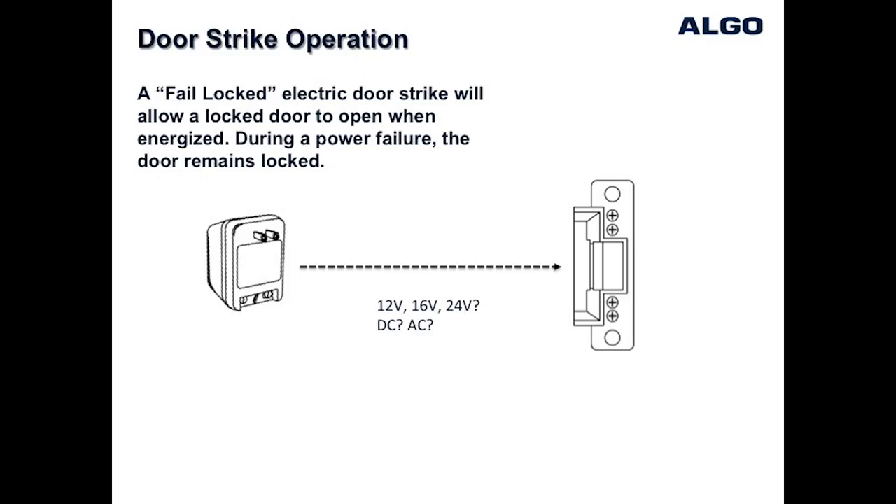There are many types of door strikes depending on the type of door jamb, and many operate at different voltages, such as 12, 16, or 24 volts DC or AC. It's important to know which voltage your door strike requires, and also to have a power supply that matches the door strike voltage.